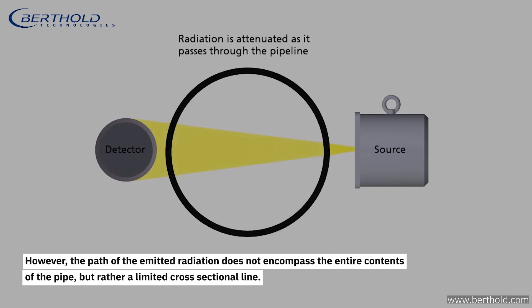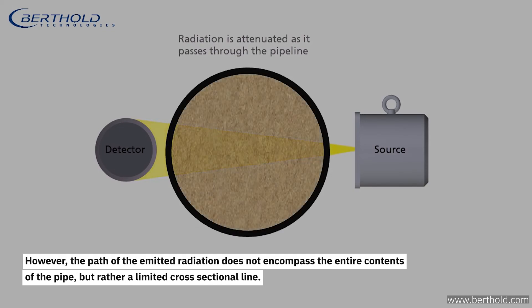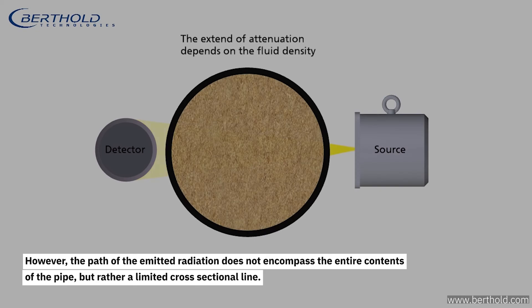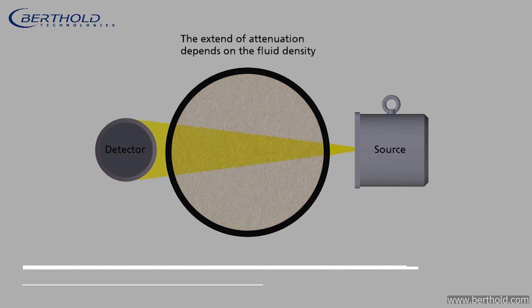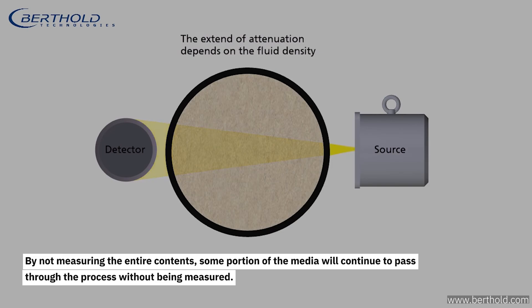However, the path of the emitted radiation does not encompass the entire contents of the pipe, but rather a limited cross-sectional line. By not measuring the entire contents, some portion of the media will continue to pass through the process without being measured.